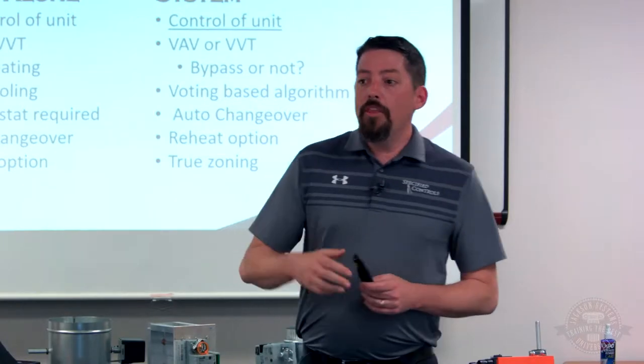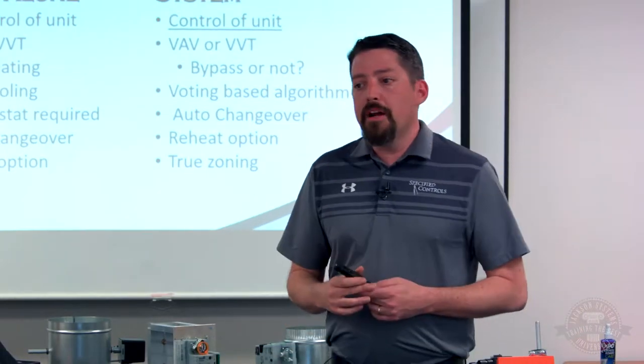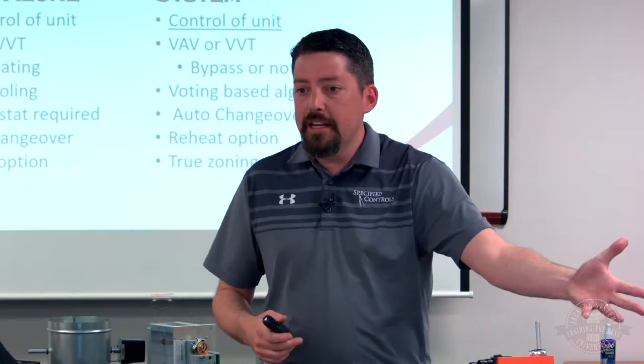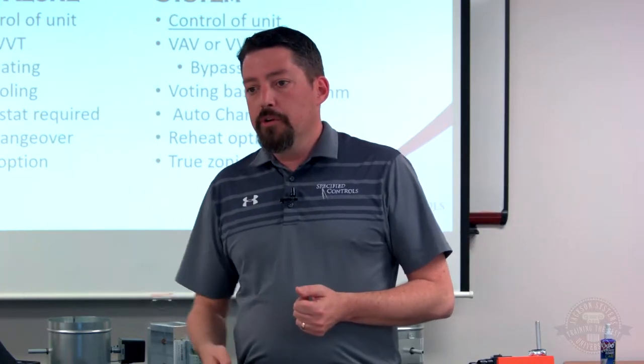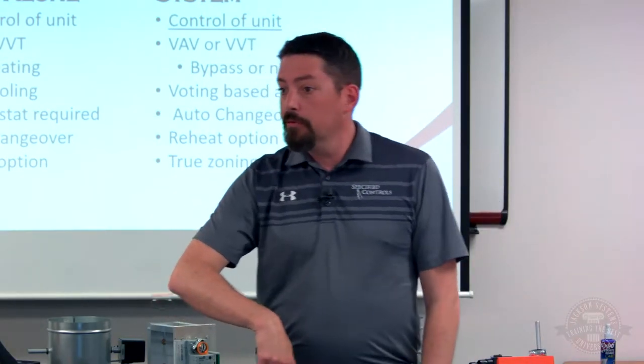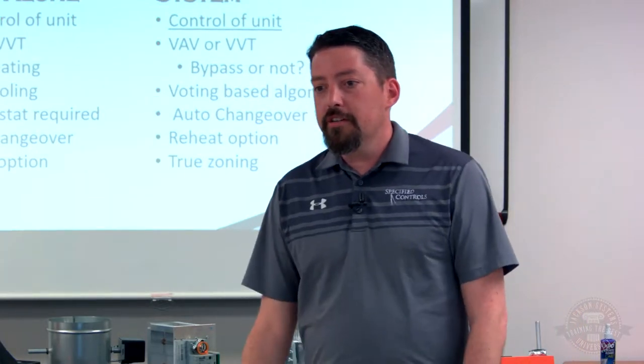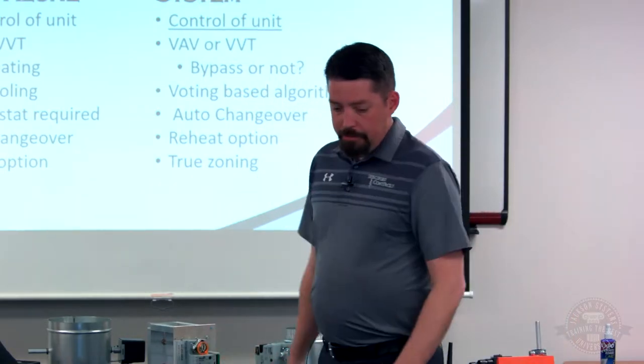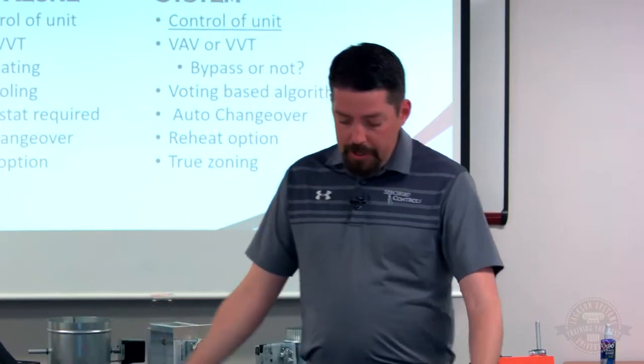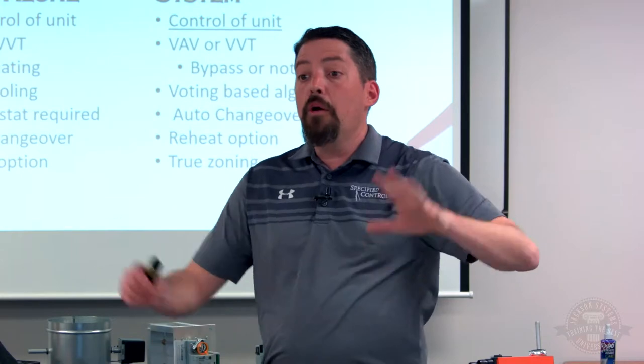Whether it's VAV or VVT, most cases use a voting system — if a majority of zones call for heating, we go heating; majority calling for cooling, we go cooling. The exception is a VAV system with reheat, where we're always in cooling — 55-degree air comes down the duct, and we heat areas that want heat while delivering cooling to those that want it. With a system we have more reheat options and can modulate heat if needed, giving us true zoning controlling all the airflow.